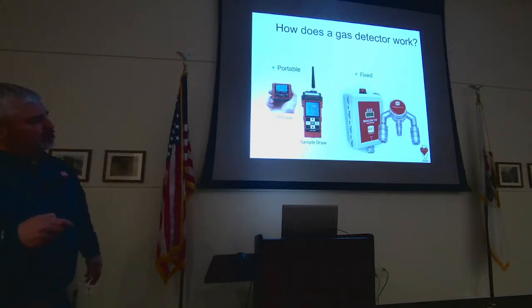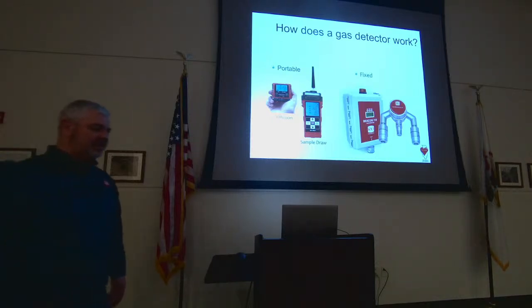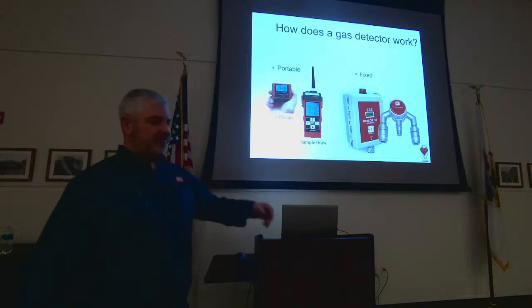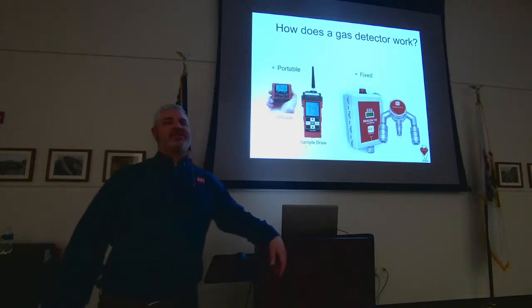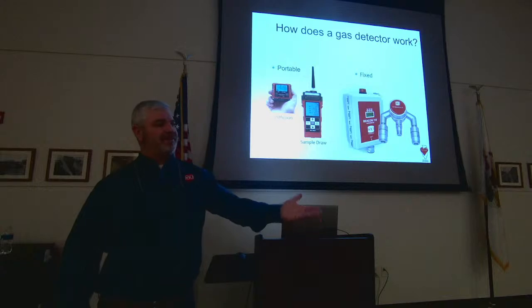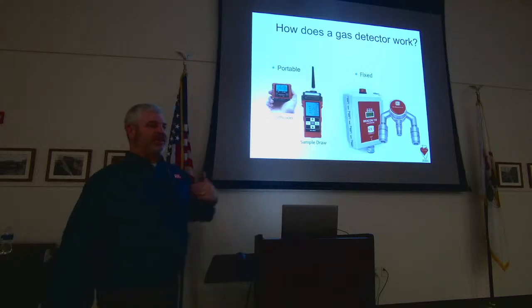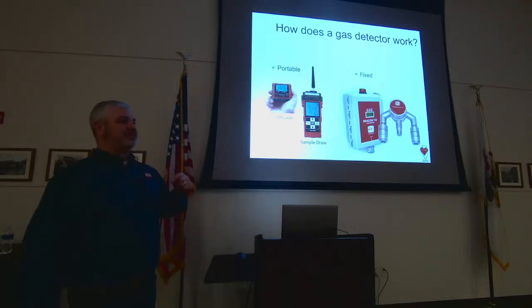There is not necessarily a plus or minus to using a sample draw instrument versus a diffusion instrument. Again, we're going to take a step back and look at the application. The simplest way to put it is, if you are going into something, you want to pull a sample out of it before you enter. The easiest way to do that is to have a unit with a pump on it to pull that sample, because you want to make sure that there's good air in there before somebody takes a step in.